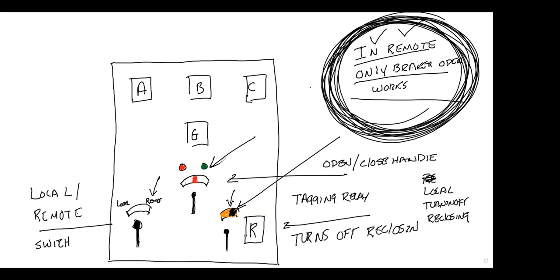Okay. All right. So really, if you want to be a relay technician or a substation maintenance guy, you can dig deeper into this. This is what a lineman needs to know. When they walk up to this, they need to know these components inside a breaker. Now, brand new employees may not happen, right? But you might walk up with somebody that's been working there for a long time and say, hey, we've got non-reclosing. And that guy says, I've done it, I worked there for many years. Oh, okay, well, I'll just turn this and make it all orange. What are you going to tell them?